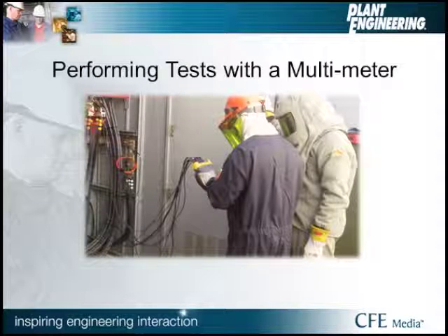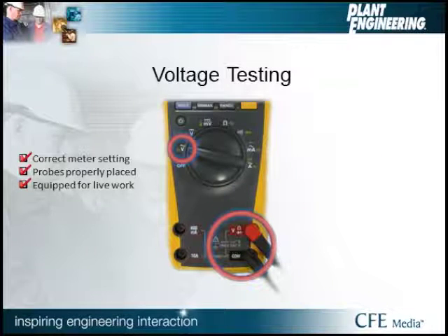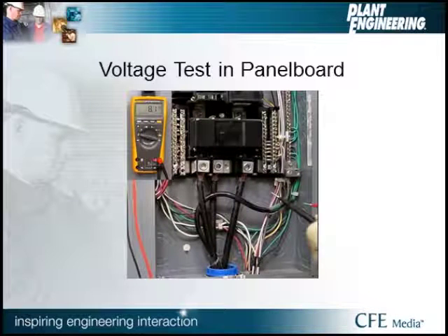So now that we've done all our pre-work, we're ready to perform our tests with our multimeters. For voltage testing, it's important that before we go in, we want to make sure that our meter is set to the correct meter setting. We want to make sure that our probes are in the proper jacks and that you have all the right equipment for the live work. In this video, we'll see voltage testing done in a panel board.